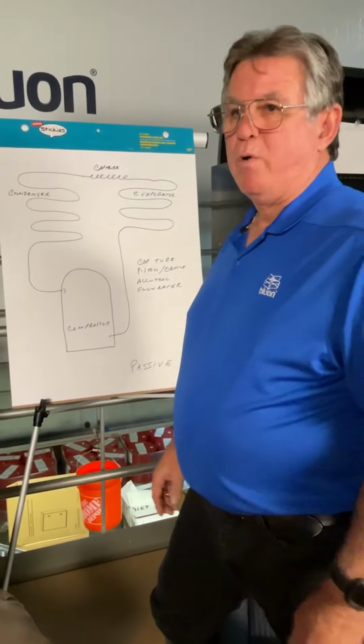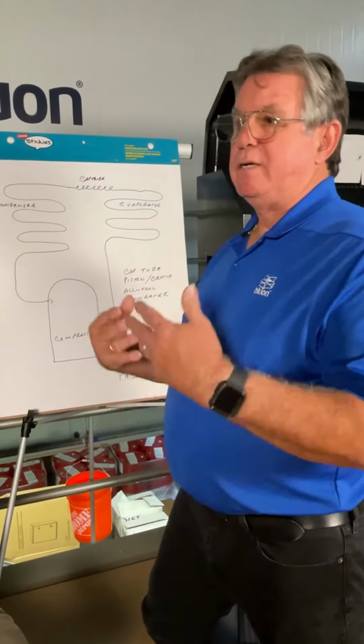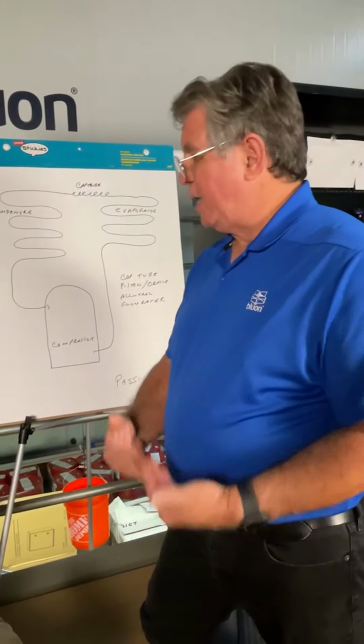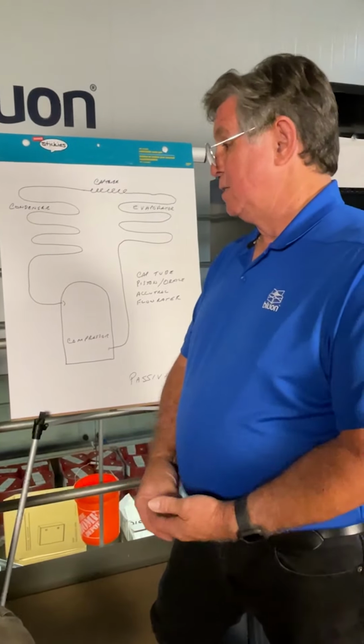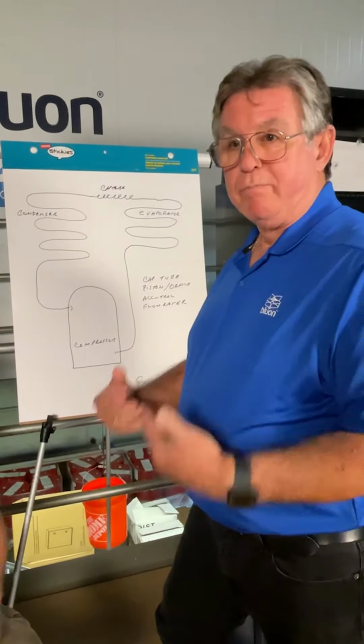They have the return air wet bulb and the outside air dry bulb. And there's also the guesstimate of here's my indoor dry bulb, my outdoor dry bulb, and my relative humidity is about, if you got a phone, you can look it up and it'll tell you where you're at and what the relative humidity is at that time where you're standing. But the one with the return air wet bulb is going to be more accurate, but the other one gives you a way to get in the ballpark, because if you got nothing else, at least it's going to get you there.